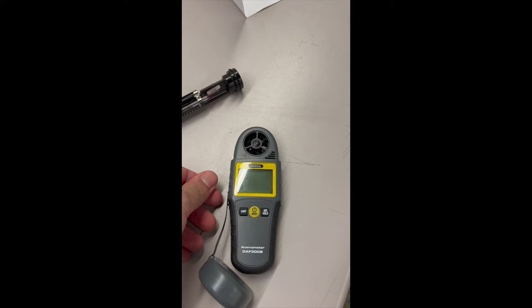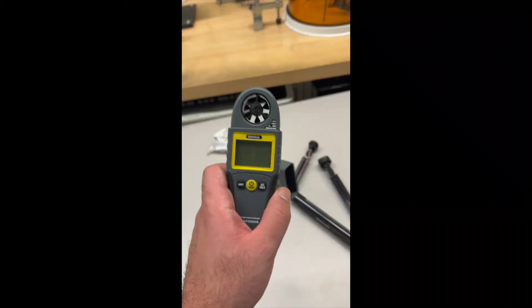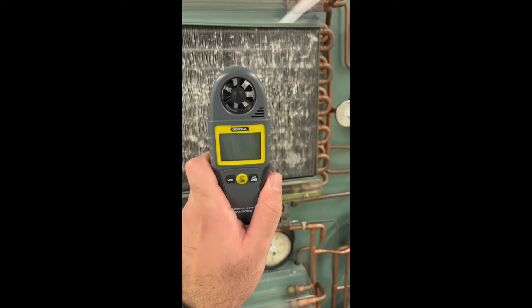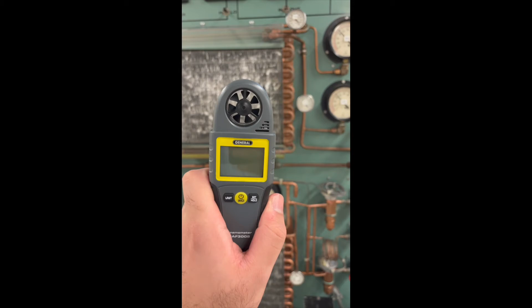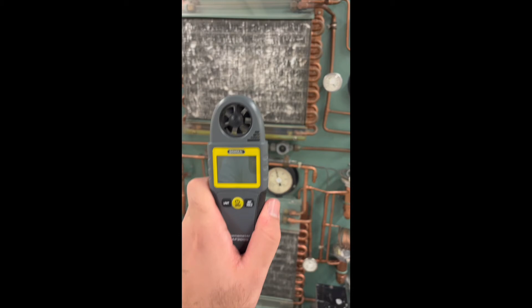One of them is this device, which is an anemometer. We have different kinds of anemometers available, but this one is a vane anemometer, which relates the rotational speed of these vanes, these turbines, to the velocity of air. So it is already calibrated, and once you put it in front of the condenser or evaporator, which blows air out, it will start to rotate and tell you what the air velocity is at the outlet. Also, this device can be used to measure temperature. As you can see, this section is used for measuring the temperature. That element is used for temperature measurement of the outcoming air. You can see other details. These are just the start, turn on and turn off buttons, and nothing more to see.